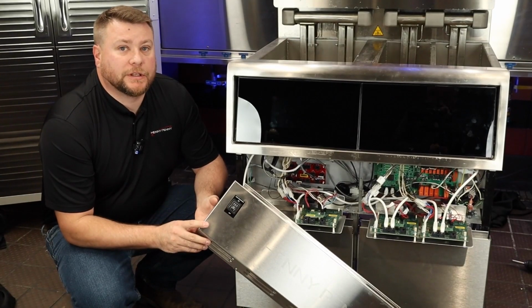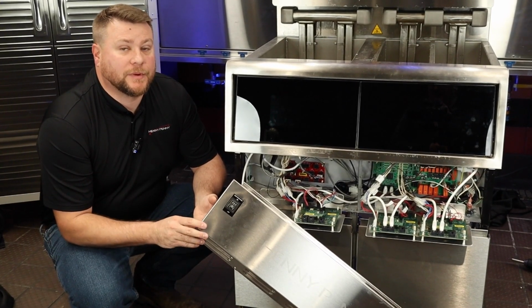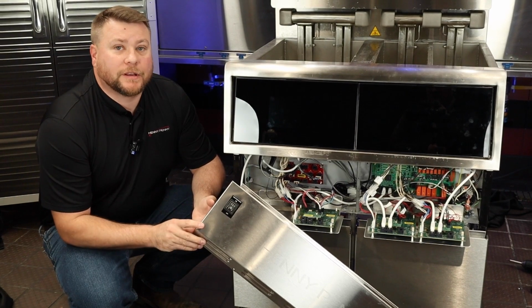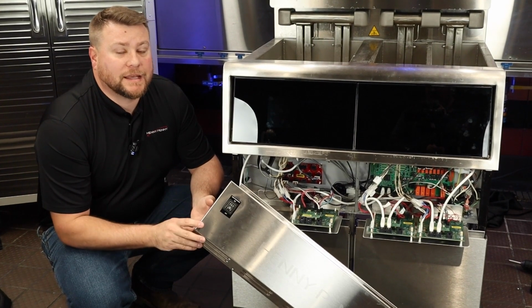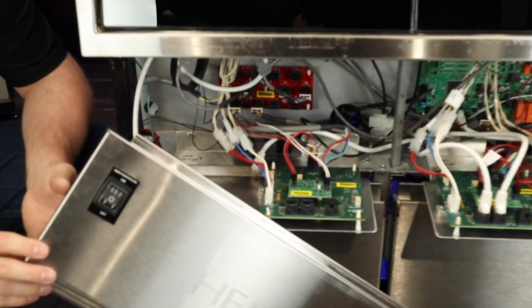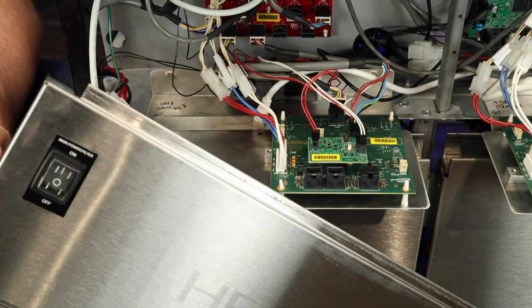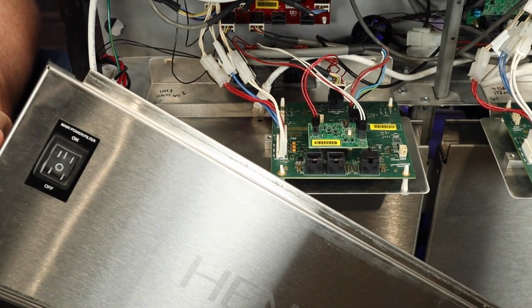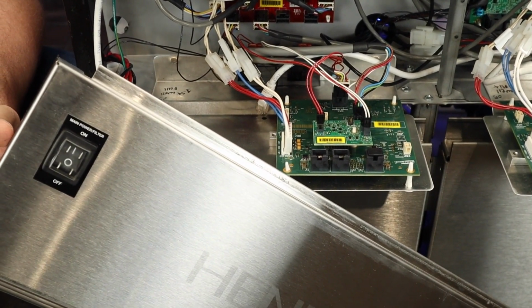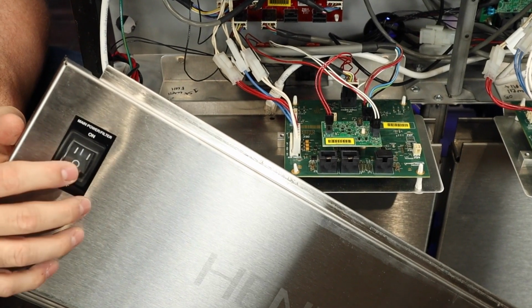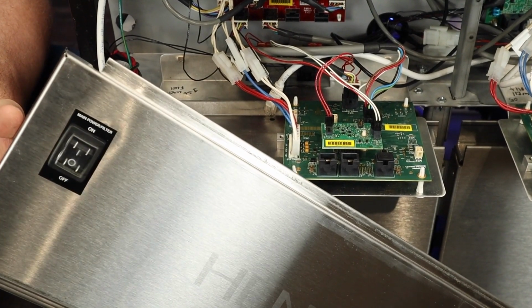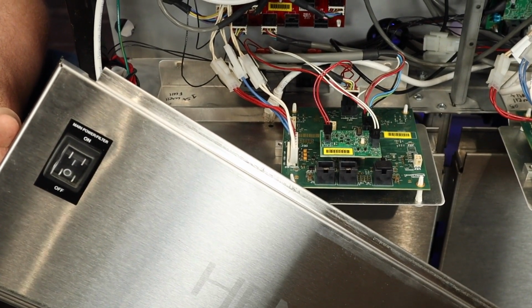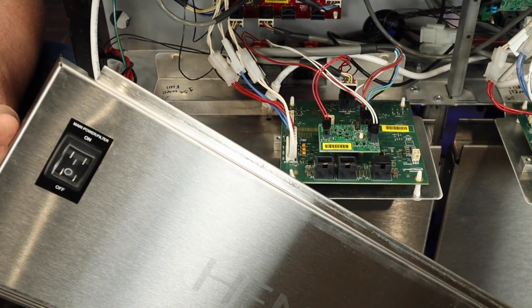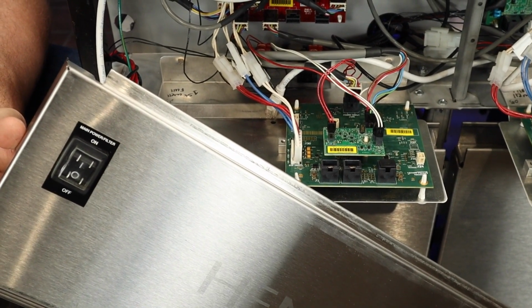When it comes to troubleshooting an E-10 on this fryer, it's not too bad. For a fryer with an active E-10 that won't reset, we can do the following. A quick way to rule out the momentary reset switch for the high limit being faulty and being the cause of the E-10 not working is to actually power down the fryer with the main power switch, and this is essentially doing the same thing that the high limit reset switch does.